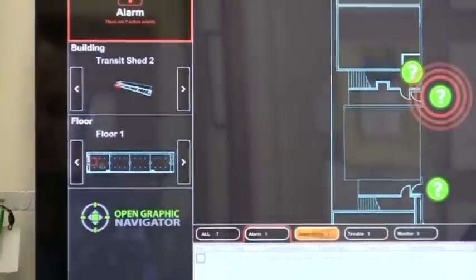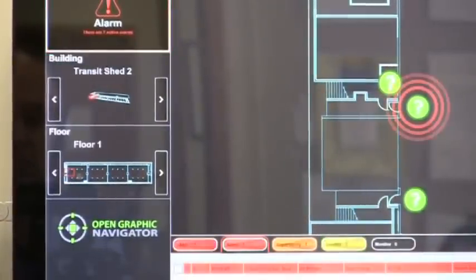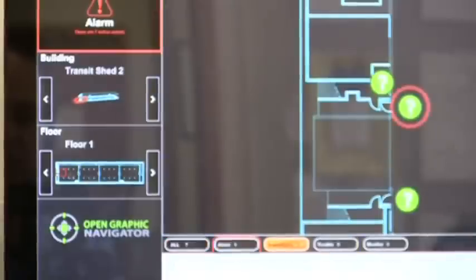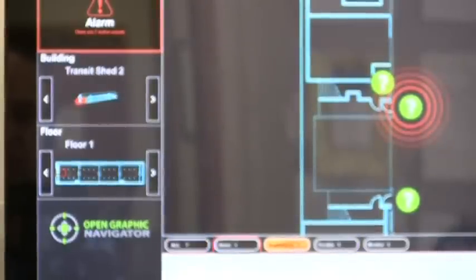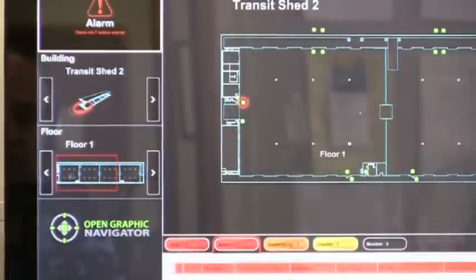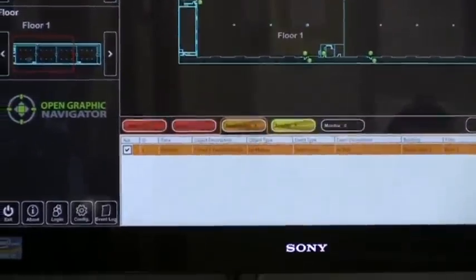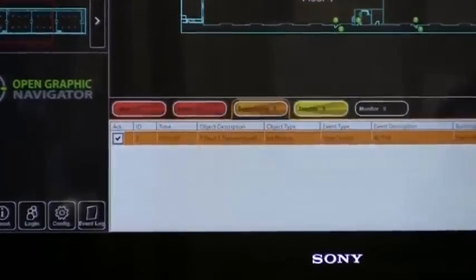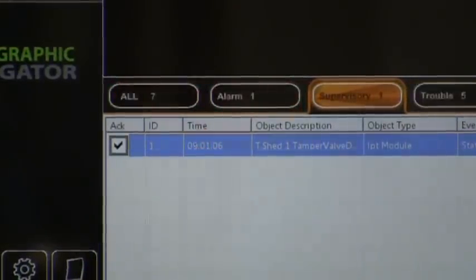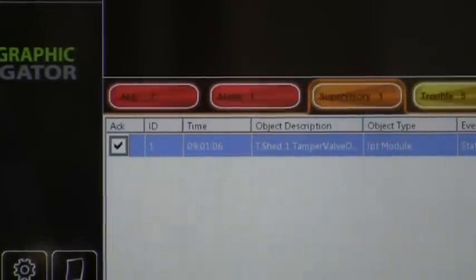If we want to see where the alarm condition is, we click the alarm tab. We can see in the building it has gone directly to the alarm. You'll notice that the supervisory condition has become a secondary item in the menu. Pinching, zooming, and panning allows us to get a better reference on where that device is located. If we want to look at the supervisory event already in the system, we click on the supervisory event tab, and by double tapping on the event itself it brings us back to where that supervisory event is located.